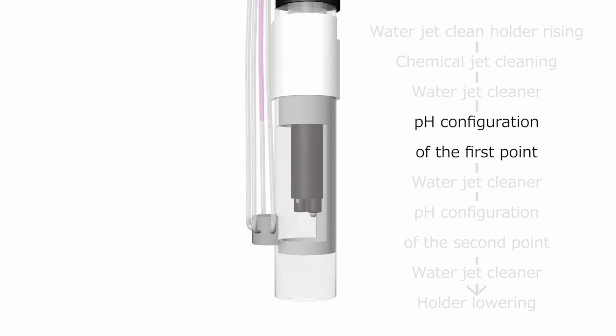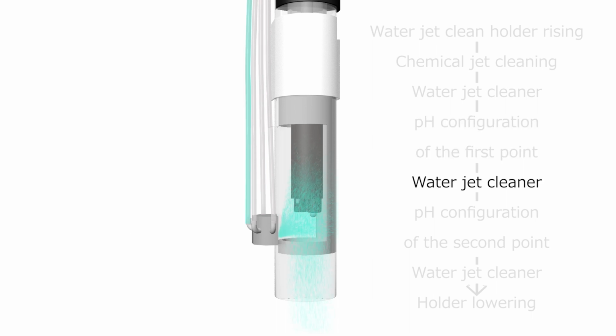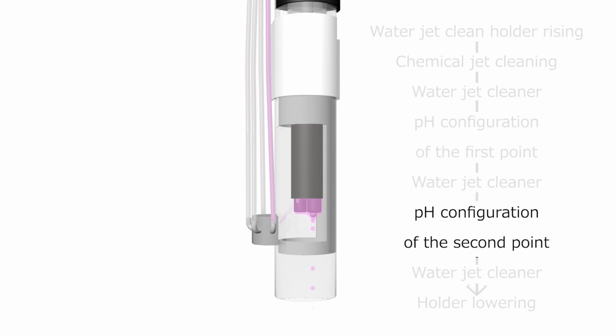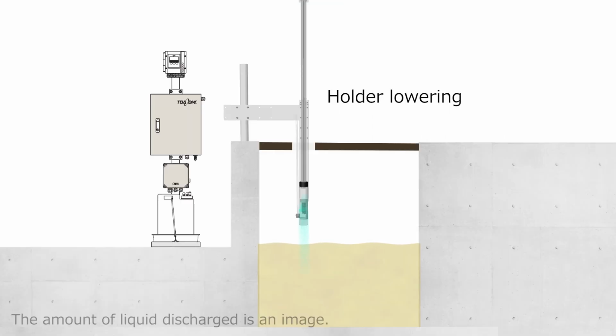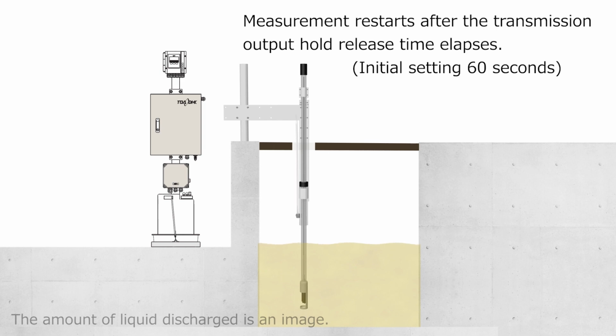The pH 7 standard solution is discharged. The sensitive part of the electrode is covered by standard solution. Then the first calibration is performed as the instrument conducts a stability check. It moves on to the second standard solution after water cleaning. When the calibration of the second standard solution is finished, it cleans with water. The holder descends and the electrode is submerged in the sample water. Measurement will resume after the transmission output hold release time is up. This is the entire series of operations.